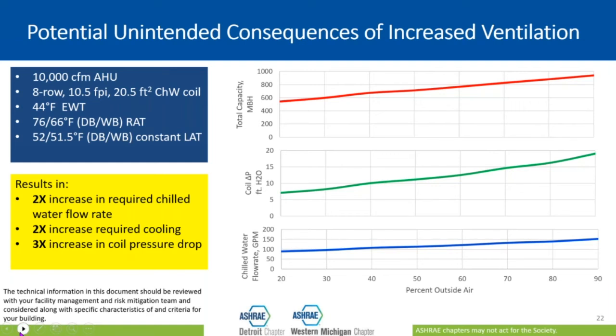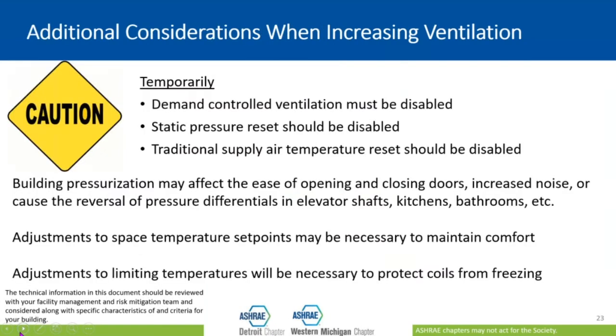Some of the things to think about when you're looking at increasing your ventilation: you're definitely going to want to temporarily disable any demand control ventilation that you may have, or static pressure or temperature controls. These things modulate your outside air based on the number of people in your space, and you don't want to be doing that right now. You want to bring in the maximum amount of outside air for which the system was designed, regardless of how many people are actually in the space. And you may have to reset some of your set points for temperature and things like that to make sure that you can keep the space comfortable. It's going to be a balancing act, right? It's going to be an iterative kind of thing.